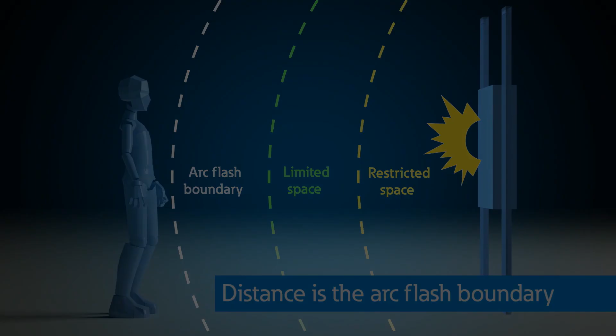The time is dictated by the protective device clearing the fault. The power is related to the amount of fault current available from all sources of power. The distance refers to the arc flash boundary, which is the point at which the arc flash energy decreases below 1.2 calories per centimeter squared.